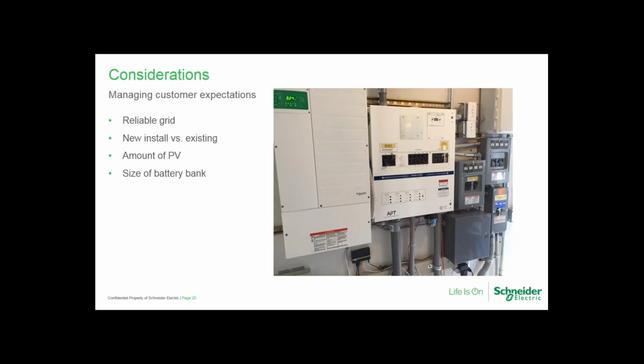It's also possible to AC couple and DC couple. If a customer lives in an area where the grid is prone to frequent outages, it is usually best to design a DC coupled system. Certainly, certain battery types may have a reduction in battery life if proper 3-stage charging occurs only randomly. If the customer has an existing PV system, AC coupling may make sense and be more cost effective.